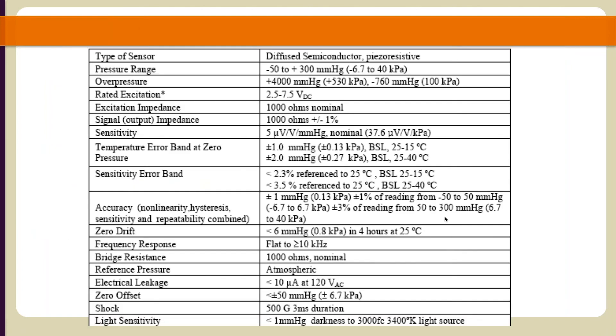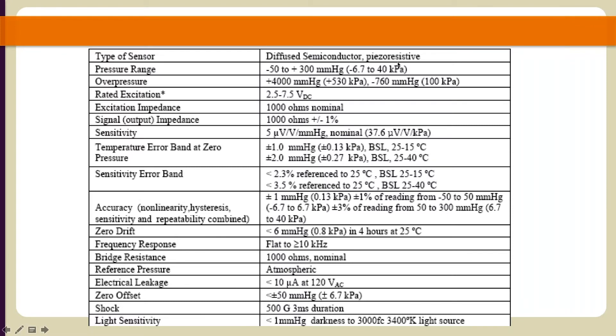I did want to point out the signal range for the Millar Microcath. Because it is designed for cardiovascular studies, it will measure within typical cardiovascular pressure ranges. For our particular sensors, that's between negative 50 to 300 millimeters of mercury — that is the linear pressure range. You can easily interface with one of our control units, the TC510 or the PCU2000, for a linear pressure range. If you were involved in studies requiring a pressure range over 300 mmHg or under negative 50 mmHg, our overpressure range is negative 760 to 4,000 millimeters of mercury.